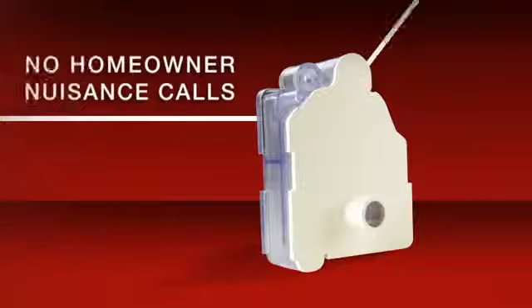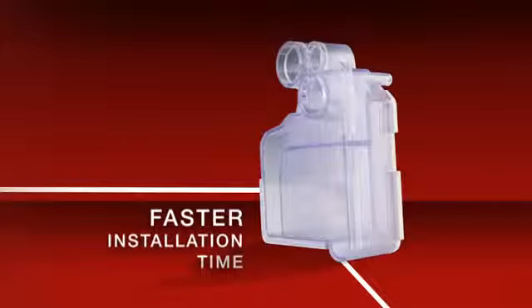One of the other things that's very helpful now is the fact that in a horizontal application, the condensate trap being only 1.5 inches instead of 4 inches is going to play a huge role because a lot of our horizontal applications, the attics are very tight and the clearances we have are minimal. So to bring that down even a couple inches is huge. No more cutting holes in platforms and rerouting things and trying to shoehorn systems in. So very, very positive in regards to that feature.